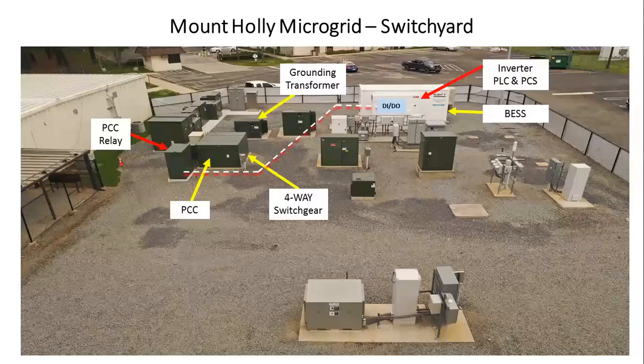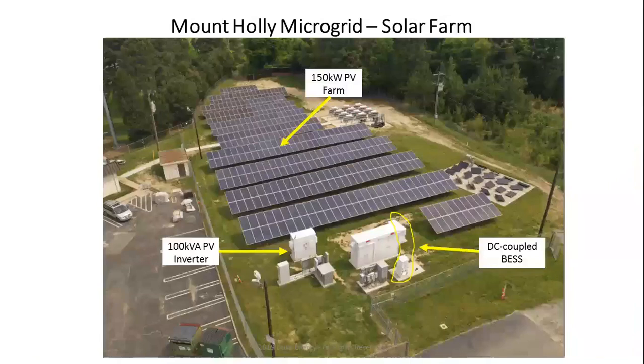So as you can see over here, we have an AC coupled battery inside this yard as one of the distributed energy resources. Then the second part of the microgrid yard, we have a PV system with a DC coupled battery. So it's a 150 kW PV farm with a 100 kVA PV inverter. Within this particular farm, you probably know there's an inverter loading ratio, that in North Carolina is between 1.2 and 1.6. And then we're going to talk about it later on.